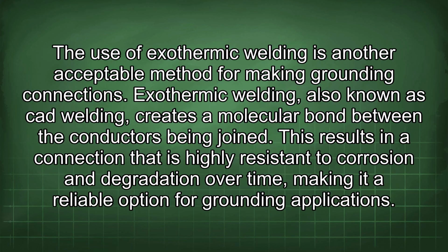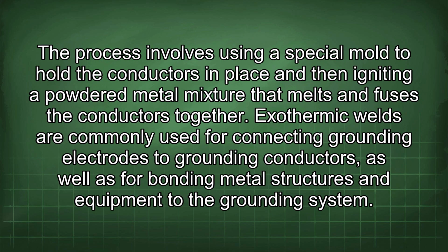The use of exothermic welding is another acceptable method for making grounding connections. Exothermic welding, also known as CAD welding, creates a molecular bond between the conductors being joined. This results in a connection that is highly resistant to corrosion and degradation over time, making it a reliable option for grounding applications. The process involves using a special mold to hold the conductors in place and then igniting a powdered metal mixture that melts and fuses the conductors together. Exothermic welds are commonly used for connecting grounding electrodes to grounding conductors, as well as for bonding metal structures and equipment to the grounding system.